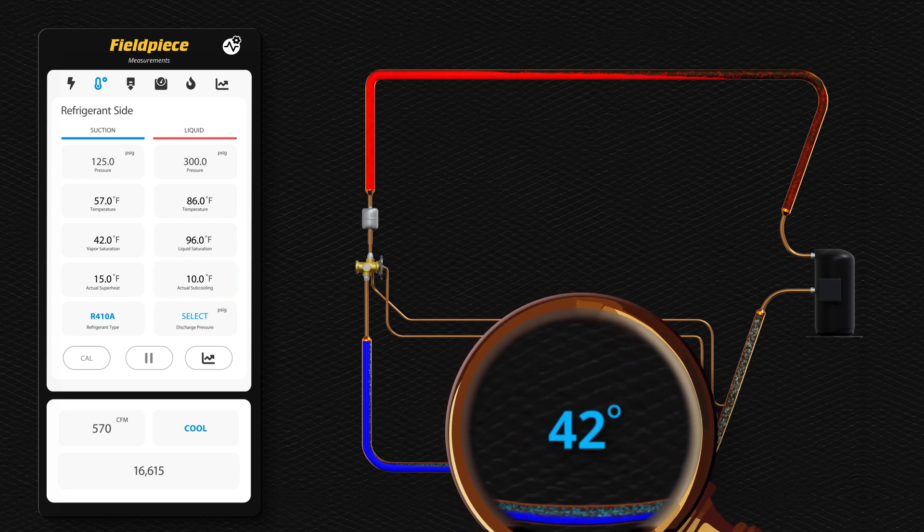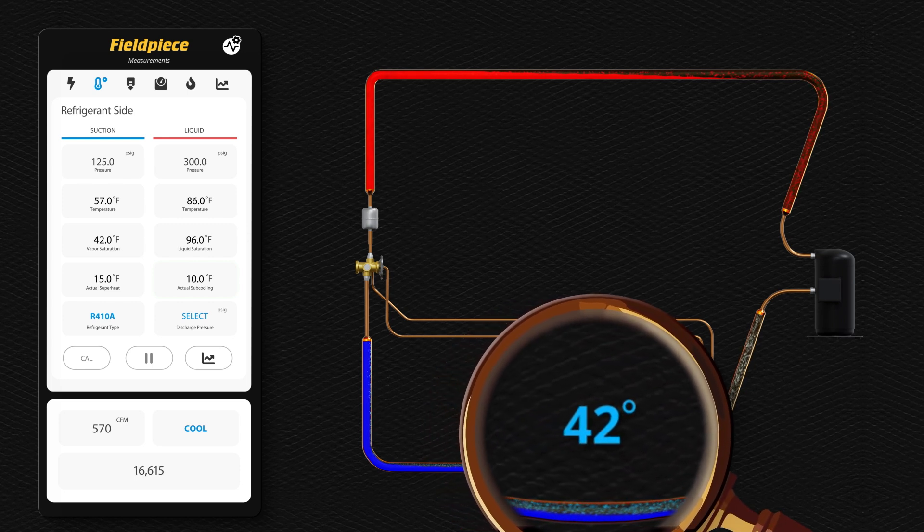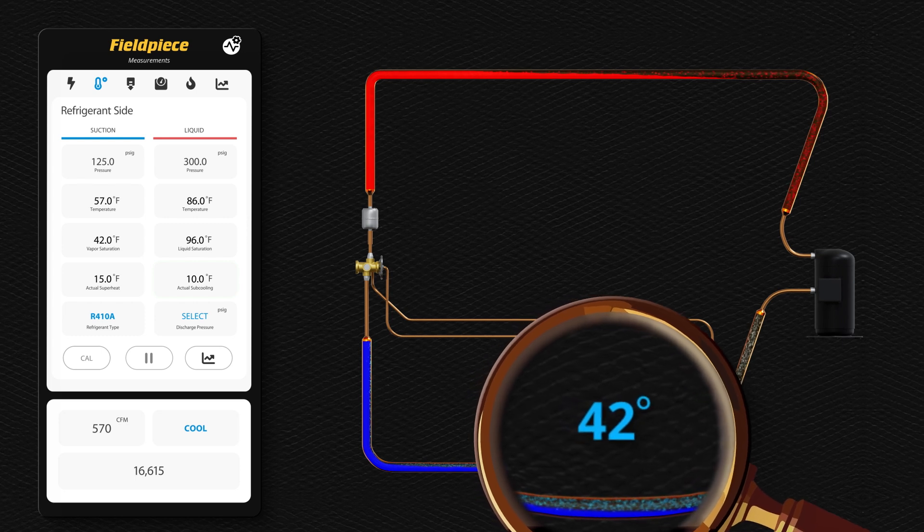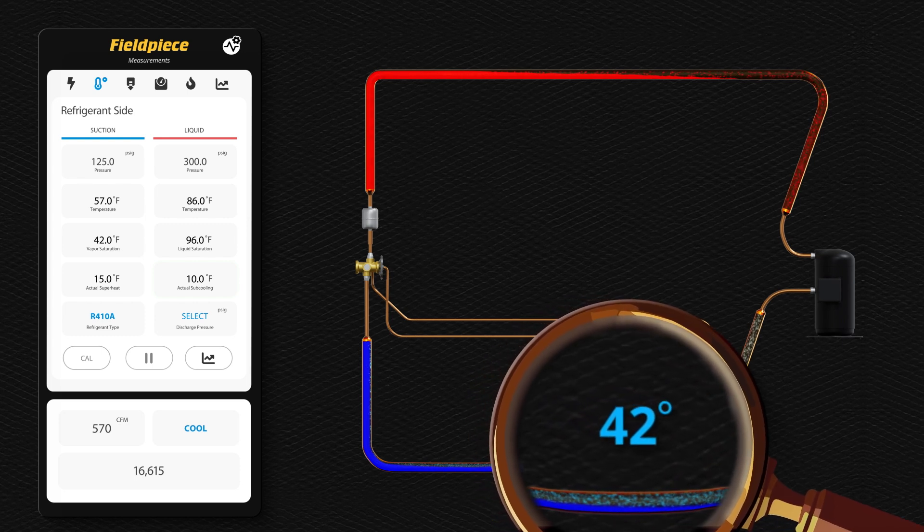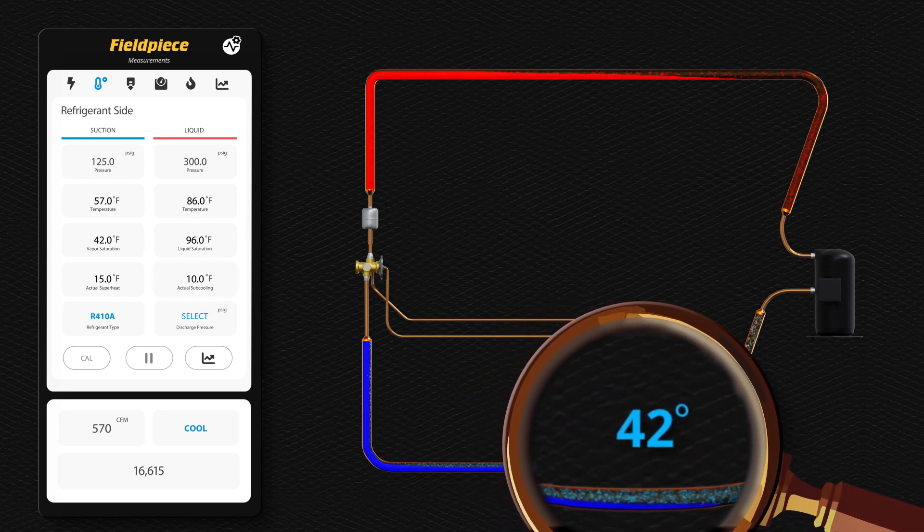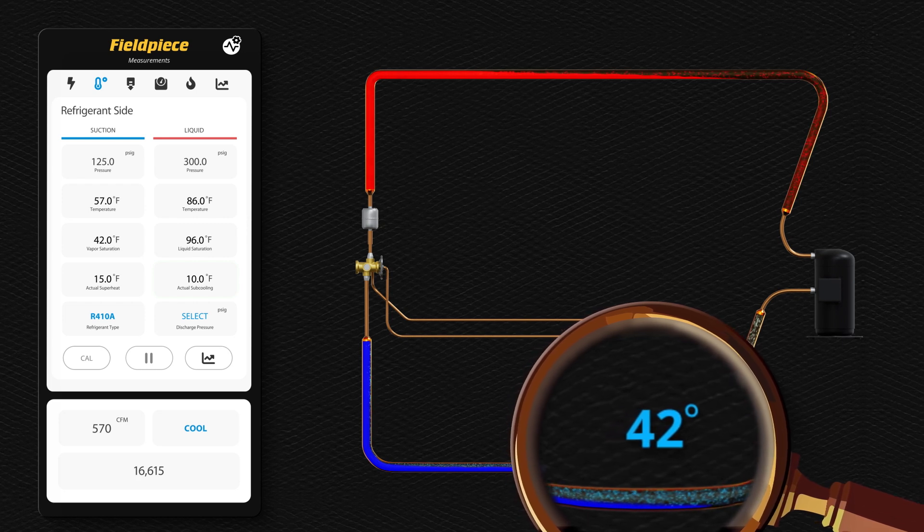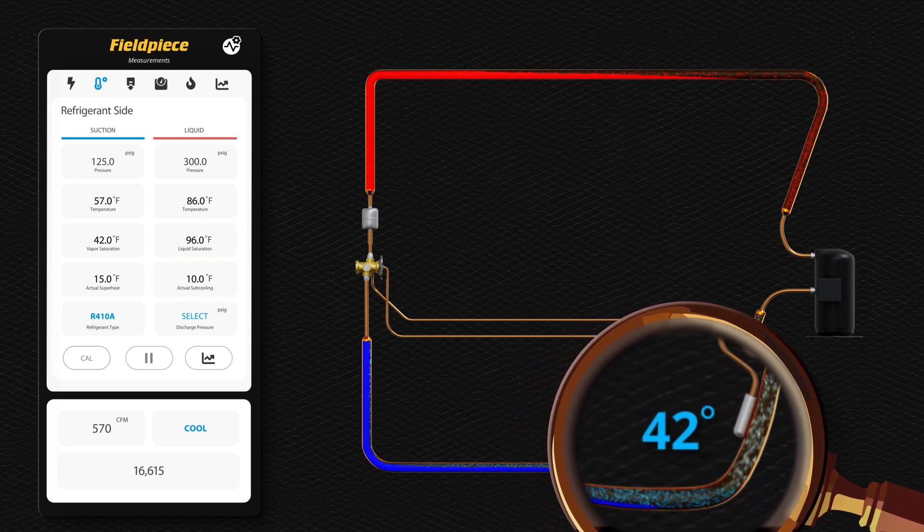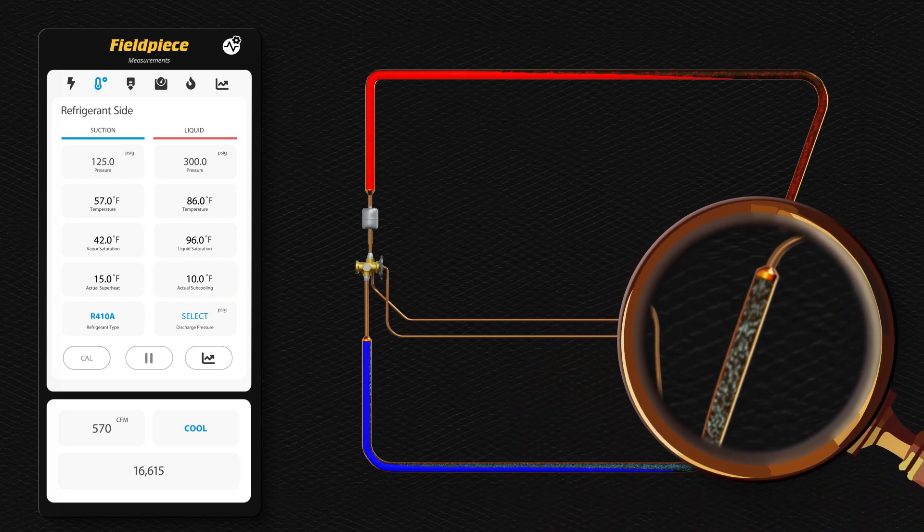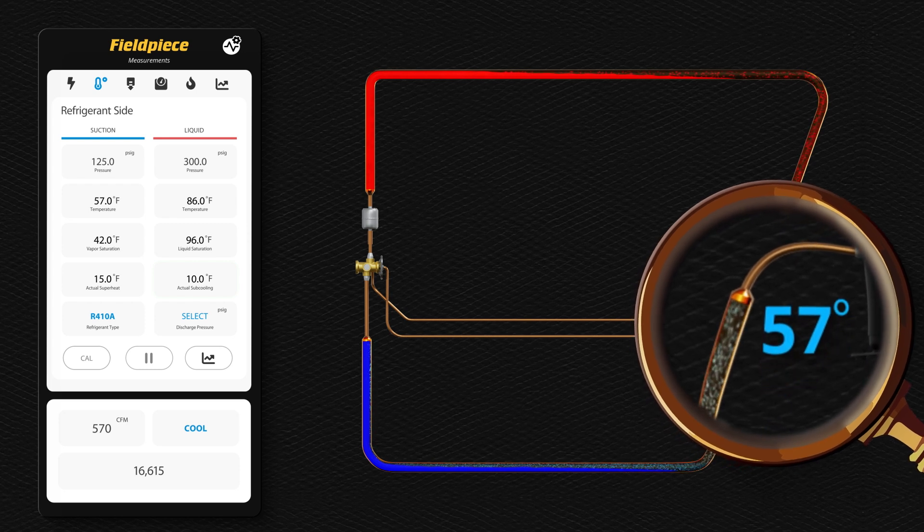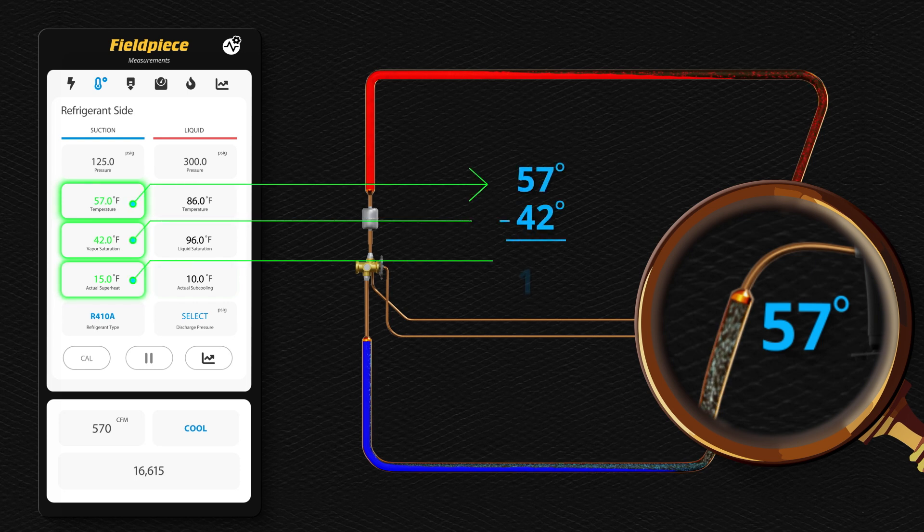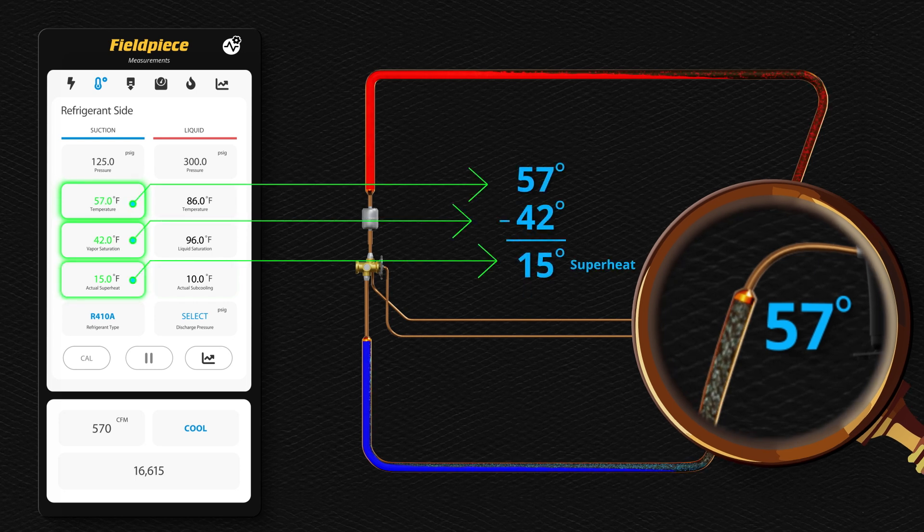As the refrigerant travels further through the circuit, the saturated temperature will remain at 42 degrees, but when the refrigerant leaves the evaporator, travels through the vapor line to the compressor, the temperature of the vapor line at the compressor is 57 degrees. Since the refrigerant is above the saturated temperature by 15 degrees, the refrigerant is 100% vapor with 15 degrees of superheat.